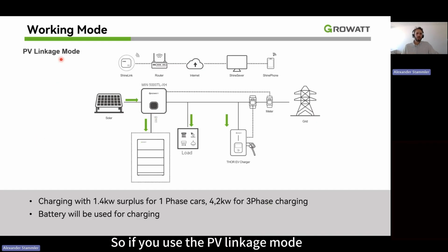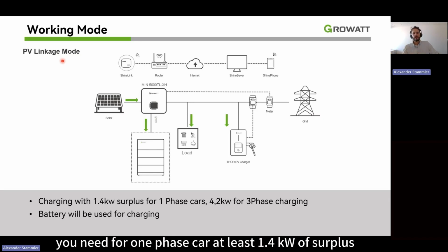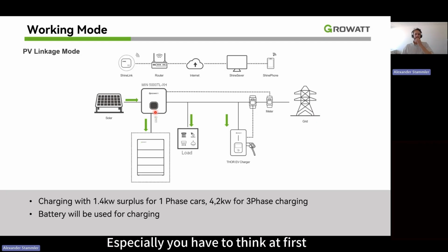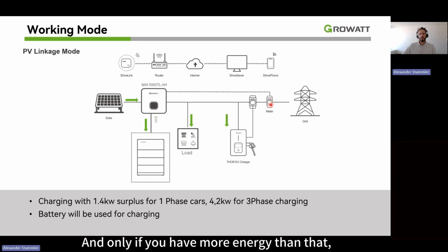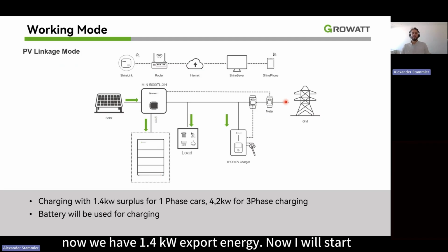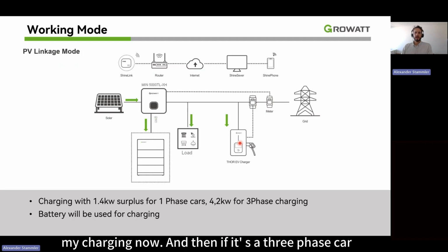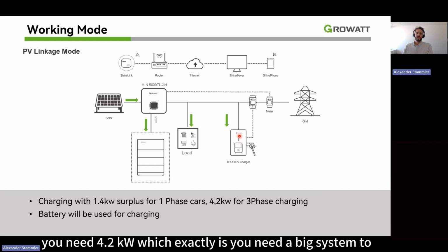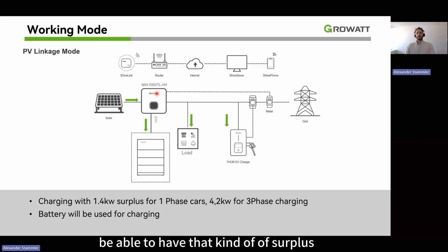So if you use the PV linkage mode, which is surplus charging, you need for a one-phase car at least 1.4 kilowatts of surplus energy, and for a three-phase car you need 4.2, which is a lot. Especially, you have to think that at first the energy will go into your battery, then it will go into your load, and only if you have more energy than that, then the EV charger will see, oh, now we have 1.4 kilowatts of export energy, now I will start my charging. And if it's a three-phase car, you need 4.2 kilowatts, which means you need a big system to be able to have that kind of surplus, especially when it's not summertime.